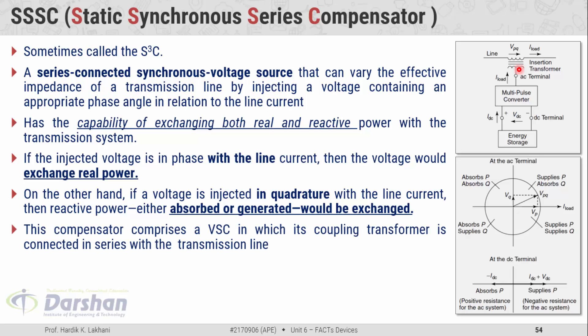This compensator comprises a voltage source converter whose coupling transformer is connected in series with the transmission line. The primary winding of the coupling transformer is connected in series with the line, whereas on the secondary side, the voltage source converter along with the energy storage element is connected. In the case of the STATCOM, the primary winding of the coupling transformer is connected in shunt with the line. That is the basic difference between the line diagram of STATCOM and SSSC.